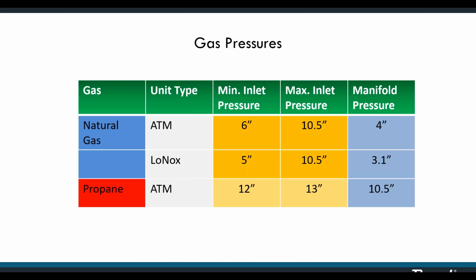The gas valve is designed to accept pressures within a certain range. The gas leaving the valve on the way to the burners will exit at a set pressure. If the incoming range is correct, the outgoing range will be also. So upon installation, check these pressures with a manometer.